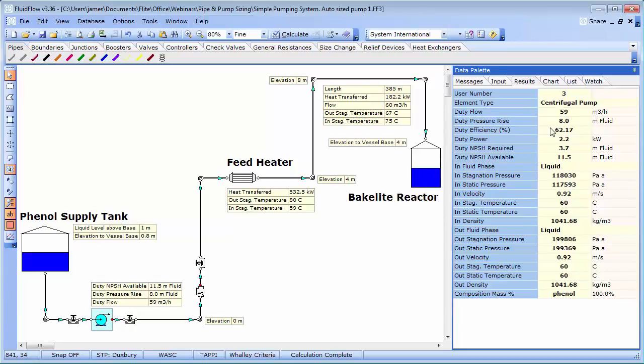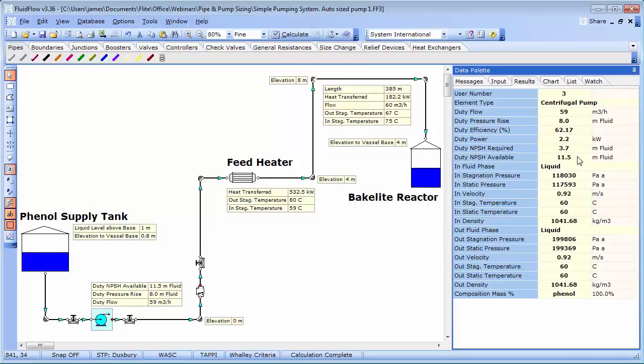the pump delivers approximately 59 m3 per hour, with a duty pressure rise of 8 m of fluid. The net positive suction head requirement is 3.7 m of fluid, and since we have an NPSHA of 11.5 m of fluid, we are within the acceptable operating limits for the pump. The efficiency is 62%, with a power requirement of 2.2 kW.